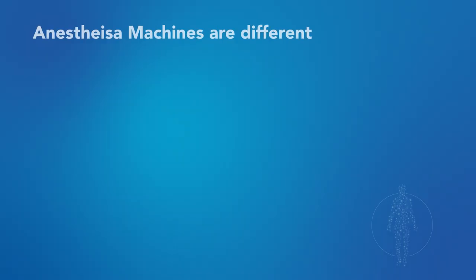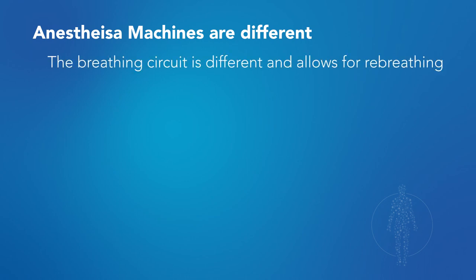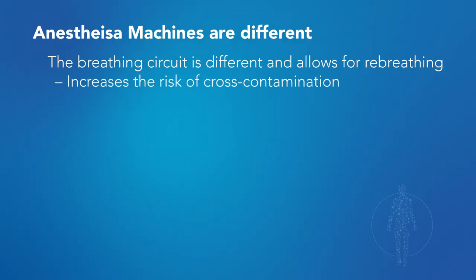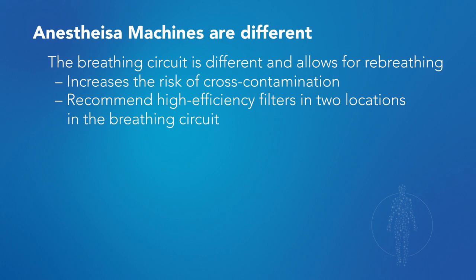Well, one of the main safety issues we're worried about is that because the breathing circuit is different for an anesthesia machine, and because the patient re-inhales gases they previously exhaled quite differently from an ICU ventilator, there's more worry that the anesthesia machines could contaminate future patients. The patient with COVID exhales into that breathing circuit, and then you bring in another patient who could potentially re-inhale pathogens exhaled by a previous patient. We are recommending, and everybody's doing this, putting high efficiency filters into the breathing passageways of the anesthesia machine to filter out viruses.